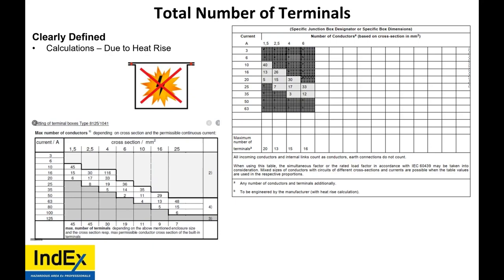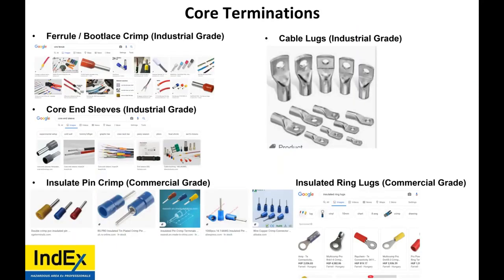Unused cores are found in all the standards. Somebody's asking about that. Look in 14, installations. Unused cores must always be terminated to a terminal and earthed back in the safe area, the non-hazardous area, so usually your LER, your substation. At the instrument end, you would have your shield drain floating, and you would not earth it at that end. Some people do, but it's not the greatest of ideas.